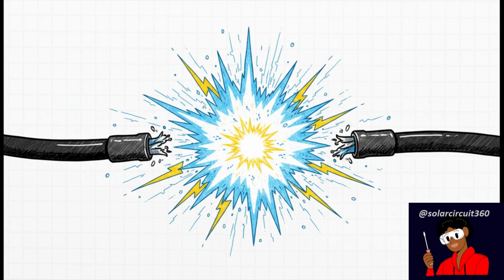And this brings us to a really harsh reality where there's just zero room for compromise. Accidental short circuits in 48-volt systems can produce severe, destructive arc conditions under high current. People constantly underestimate 48-volt setups because they safely categorize them in their heads as low voltage. But let me be super clear about this. Low voltage absolutely does not mean low danger when you have massive current potential sitting right behind it. If a positive and negative accidentally touch, or if a high current connection pops off under a heavy load, it can pull a severe, blinding arc. And trust me, you can never, ever rely on just cable insulation to protect you from that.